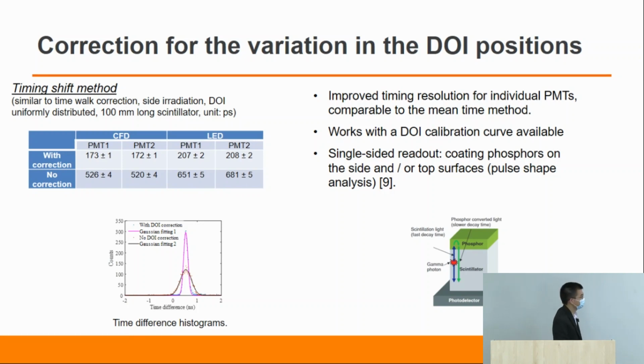You can see from this table, the timing resolution measured with individual PMTs can be improved from 526 picoseconds to 170 picoseconds for this PMT, similar for PMT2. And this is a very big improvement, I think. This approach can work as long as we have a depth of interaction calibration curve. For a scintillator read out by only one PMT, we can get this information by putting some phosphor on the side or the top surface of the scintillator, with a scintillation decay time different from the scintillation decay time of the scintillator itself. Based on the pulse shape analysis, we can get the depth of interaction position continuously. So you can see very easily the improvement of the timing resolution by correcting for the depth of interaction variation for the single-sided readout.